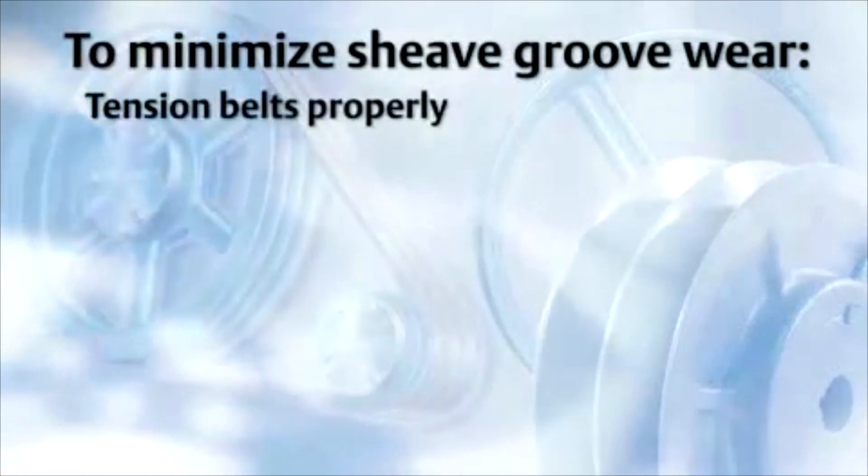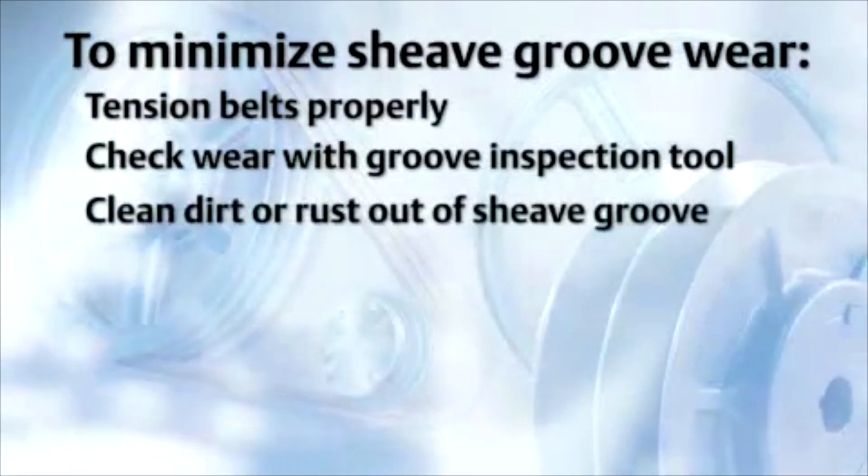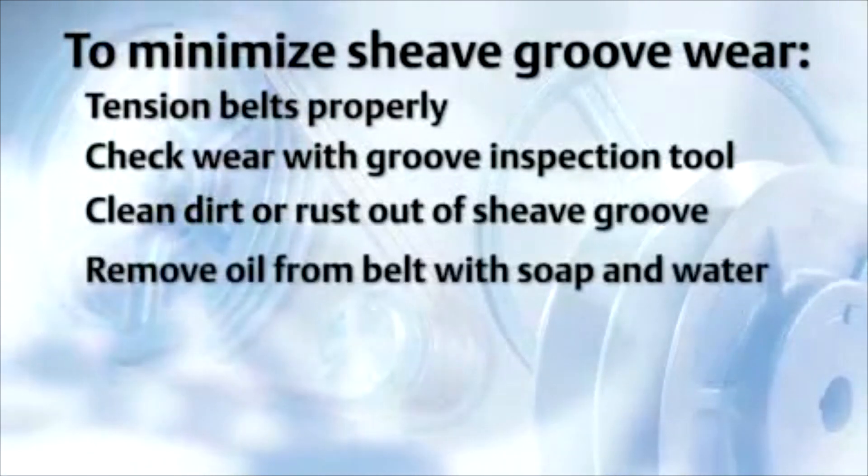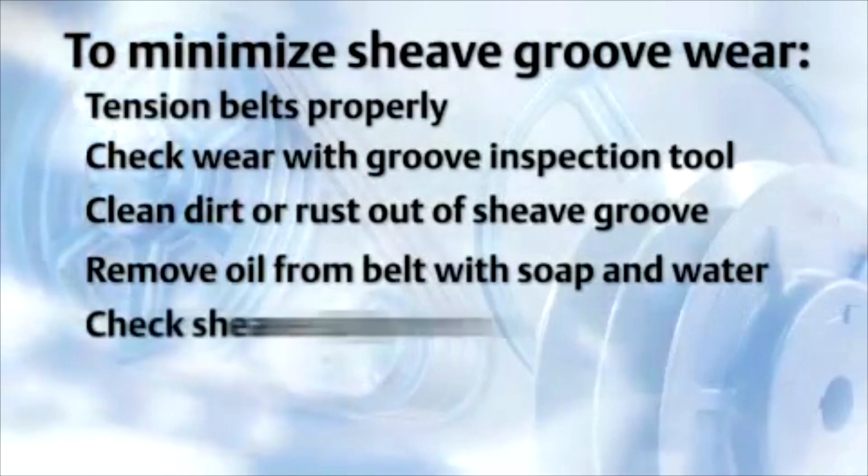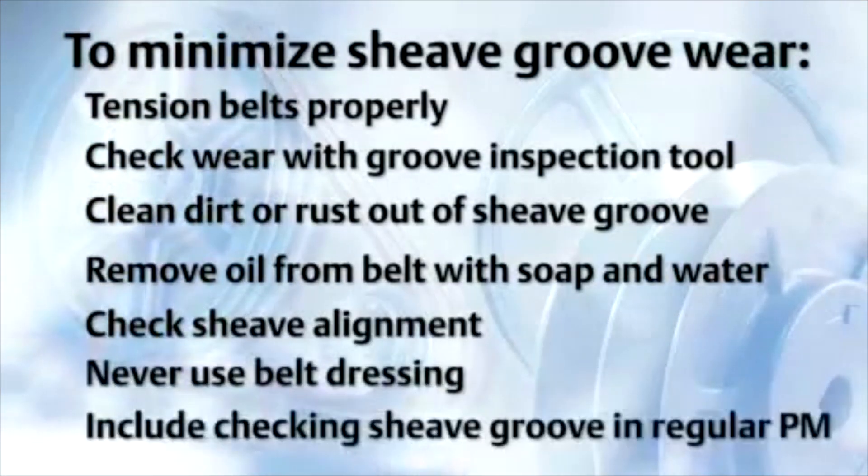To minimize sheave groove wear: tension belts properly, check wear with groove inspection tool, clean dirt or rust out of the sheave groove, remove oil from belt with soap and water, check sheave alignment, never use belt dressing, and include checking sheave groove in your regular preventive maintenance procedures.